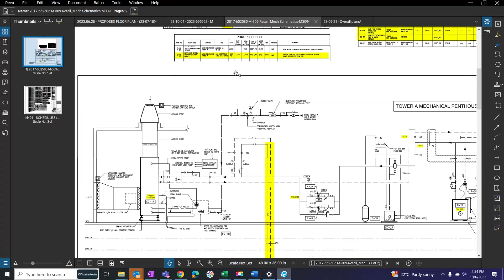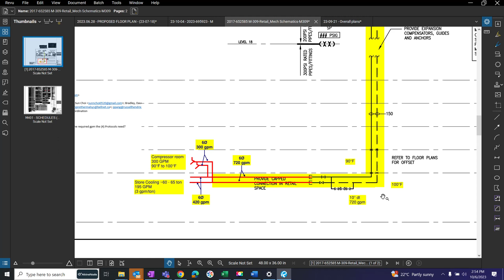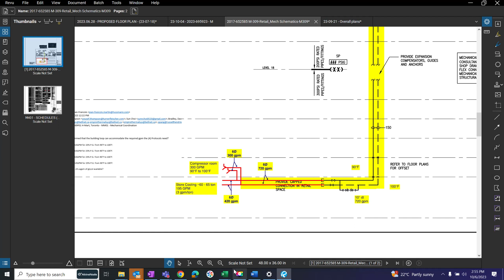If you send us 90-degree water for us to condense into when we're running an AC, that's like the hottest day of an air-cooled condenser, so we're going to struggle even though you've got a chiller running. It'll do it, but it's like putting it on the hottest day all the time. You just wonder whether that number's too - I don't think it's what it's actually providing, perhaps.